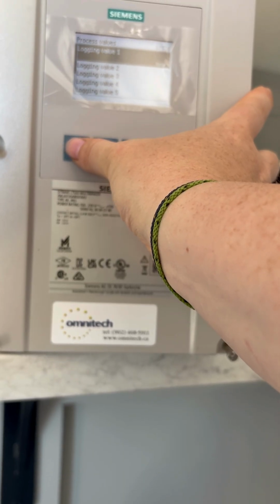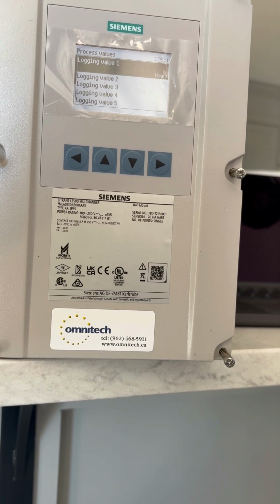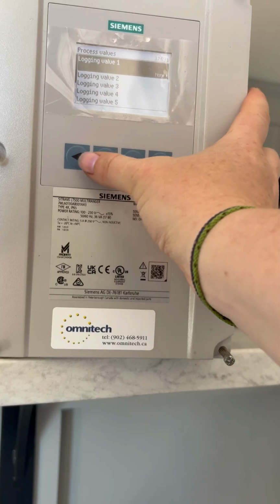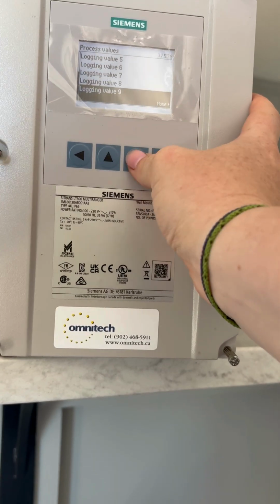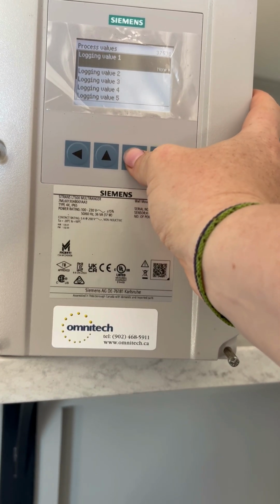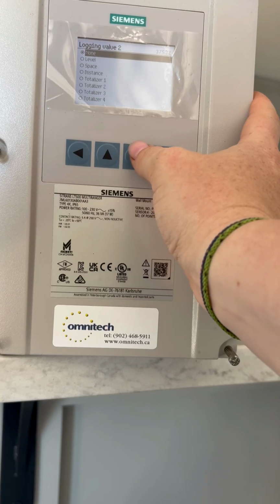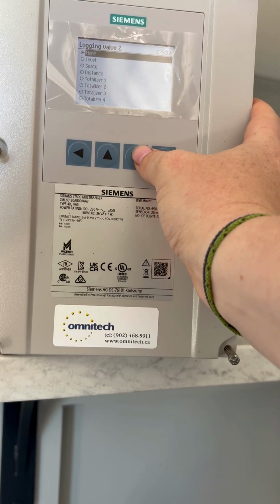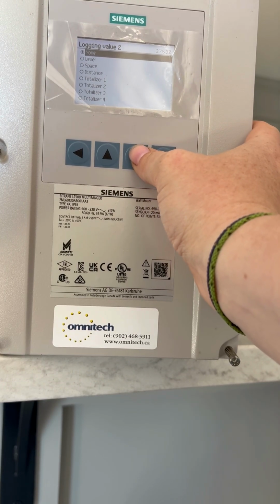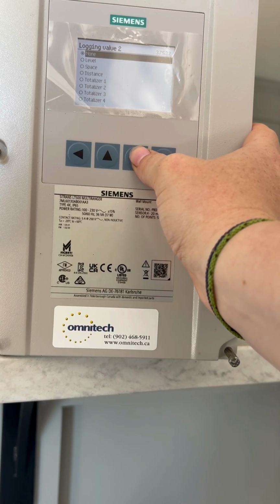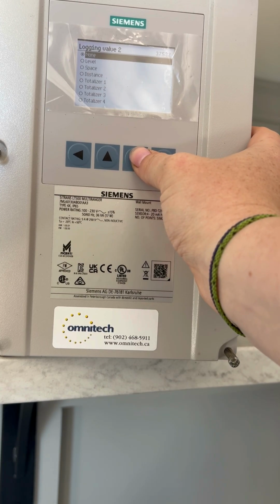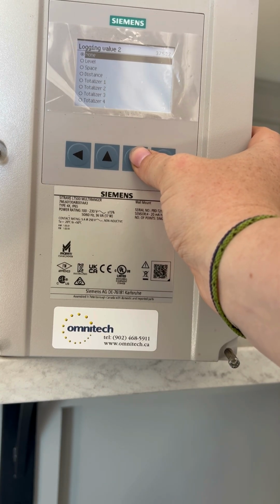So basically I'm just going to be logging the level every 5 minutes. If we wanted to come back, grab that SD card and load it up to the computer, you could take a look at what that was. You have all the way up to 7 values. I don't see any other value that I personally would want to. Maybe the totalizer if you needed that, but that would be more of a volume application, how much you're consuming. So maybe you do want to use that, but that's up to you if you want to set that up.